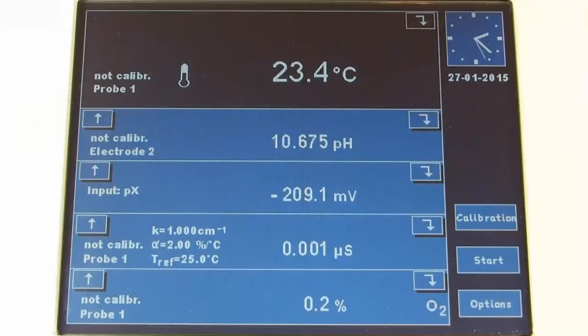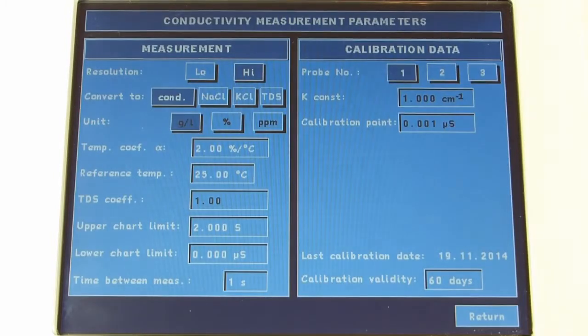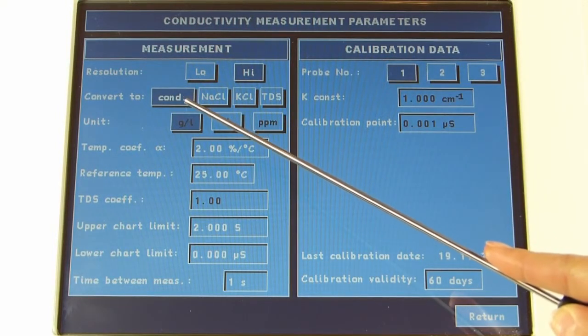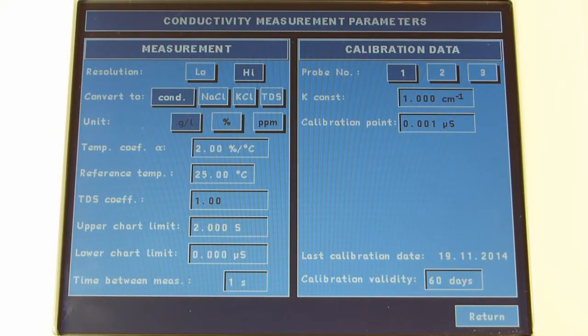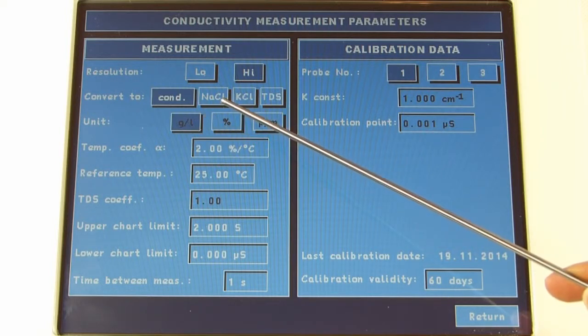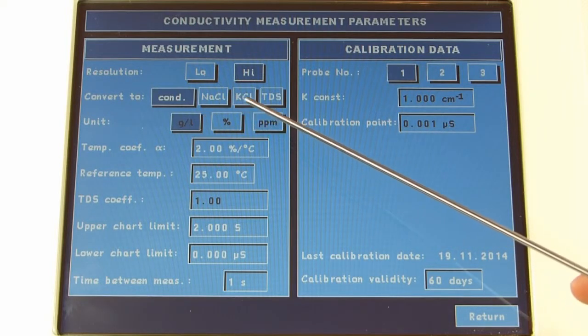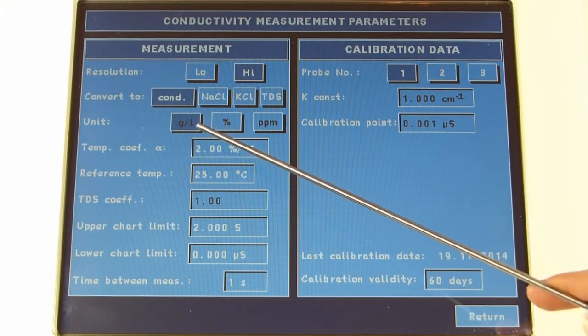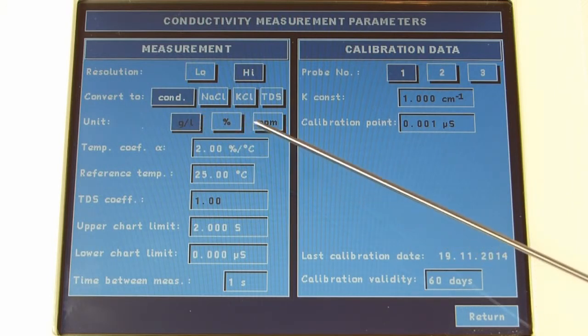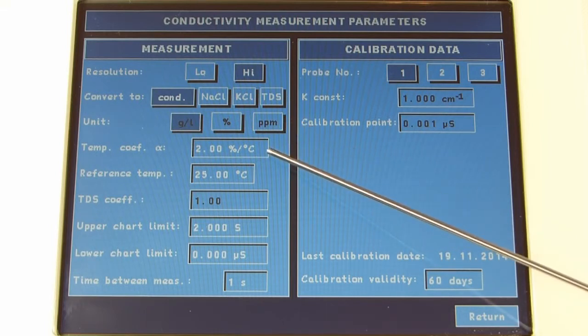In case of conductivity measurement, we may enter the parameters screen and choose the kind of measurement. Conductivity, measured in microsiemens or millisiemens. Salinity, the result is calculated to NaCl, KCl or TDS. Choose the unit in which the measurement will be made. It is also possible to enter the alpha coefficient value, which will be calculated during the temperature compensation.